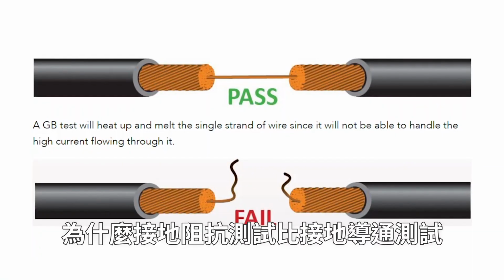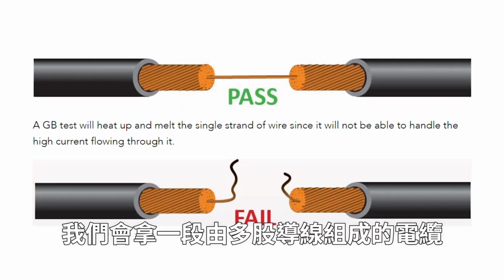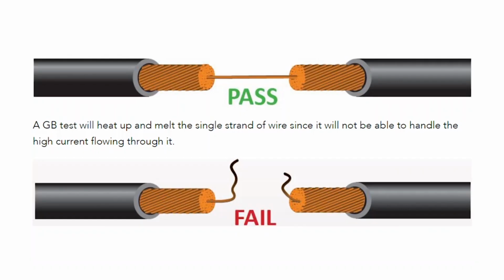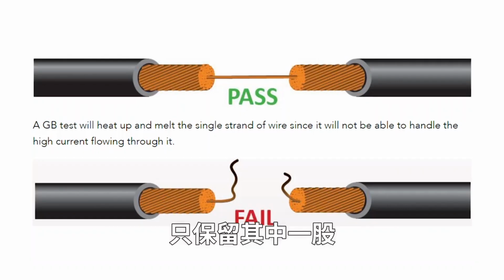So now let's take a look at why the ground bond test is the more stringent of the two test types compared to the ground continuity test. In our example, we will show you a piece of cable with multiple strands, and if we were to cut out all strands but one and perform a continuity test from one side of the cable to the other, it will result in a pass.